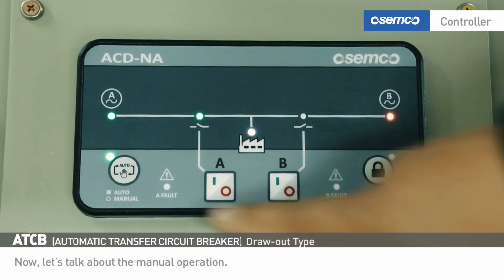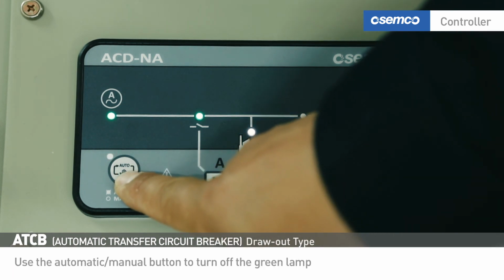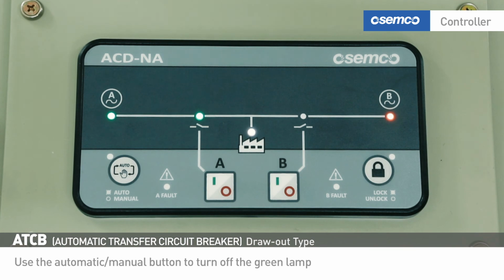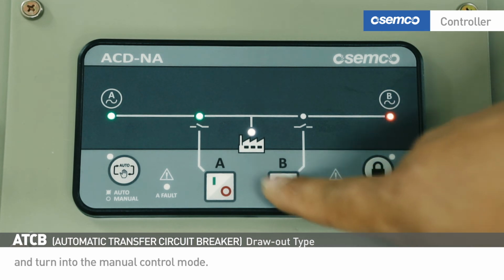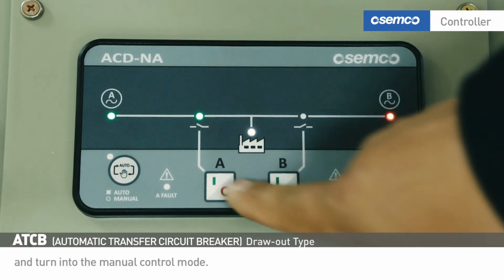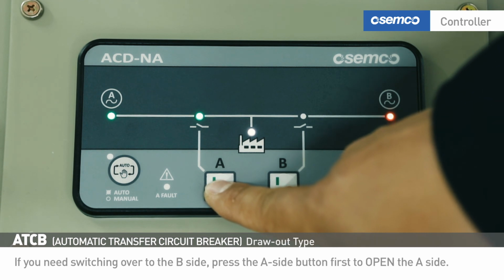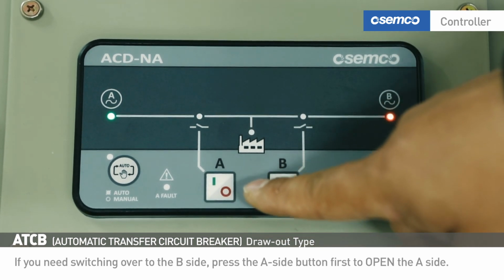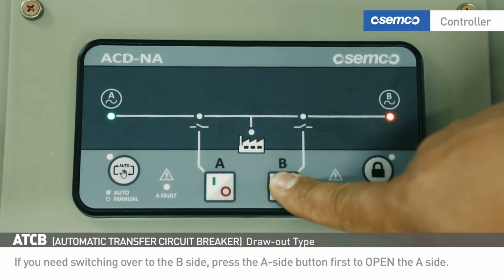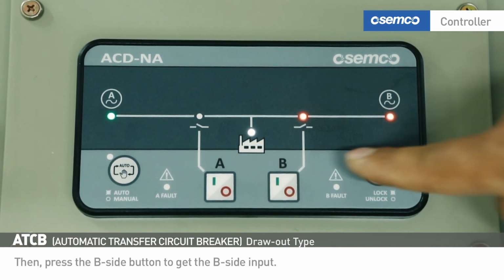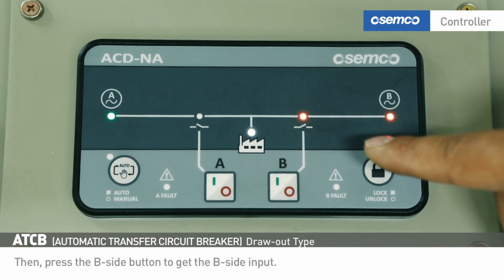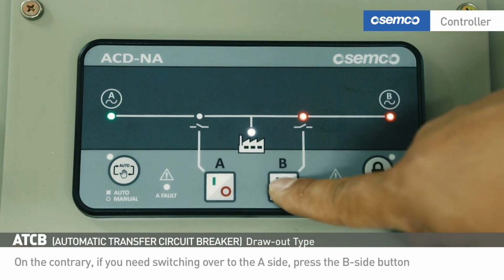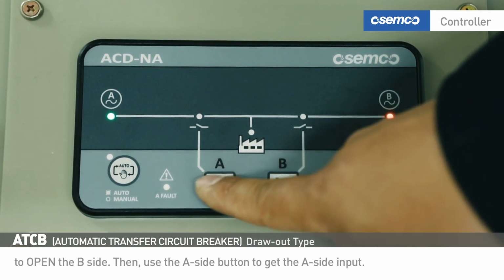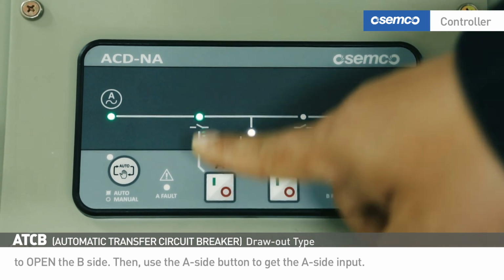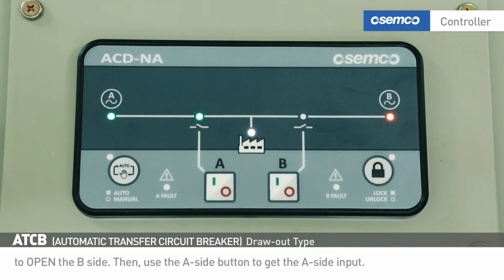Now, let's talk about the manual operation. Use the automatic manual button to turn off the green lamp and turn into the manual control mode. If you need switching over to the B side, press the A side button first to open the A side. Then, press the B side button to get the B side input. On the contrary, if you need switching over to the A side, press the B side button to open the B side. Then, use the A side button to get the A side input.